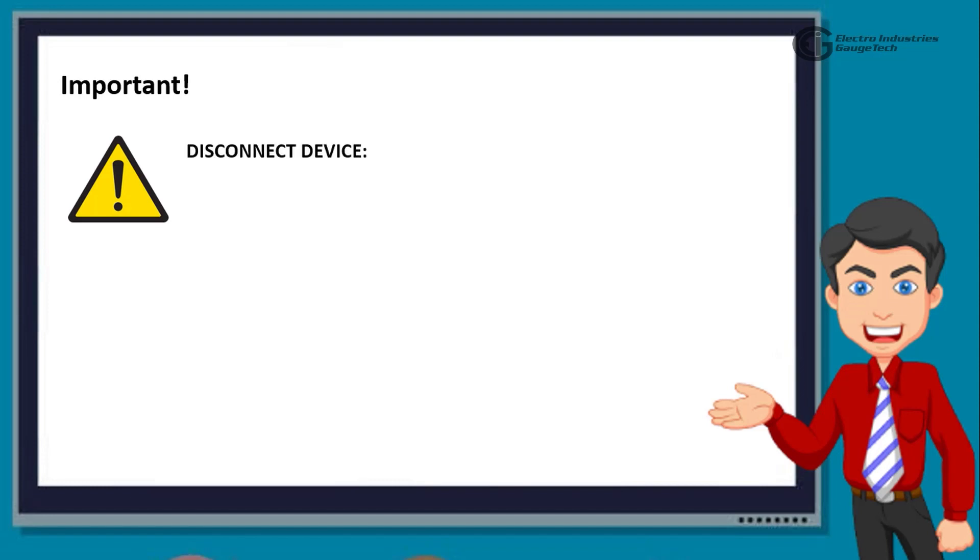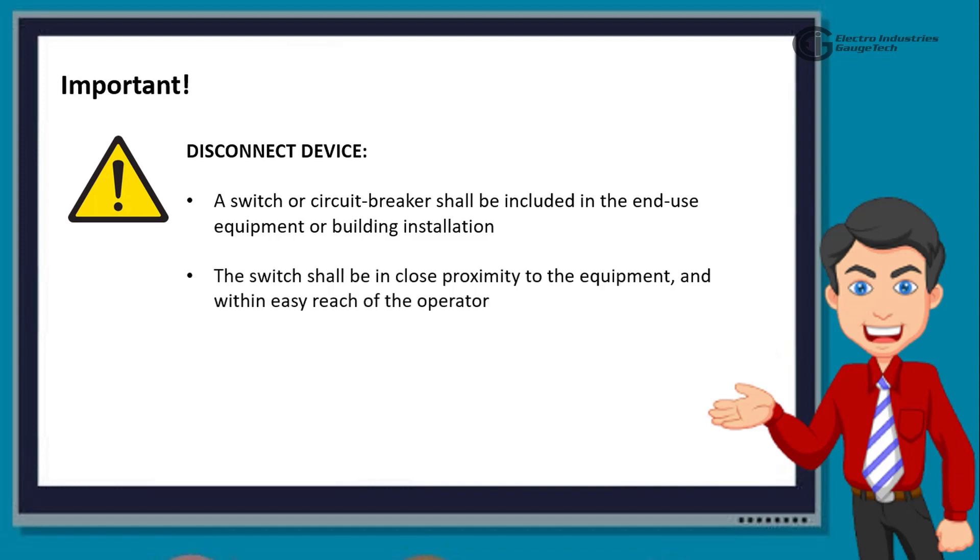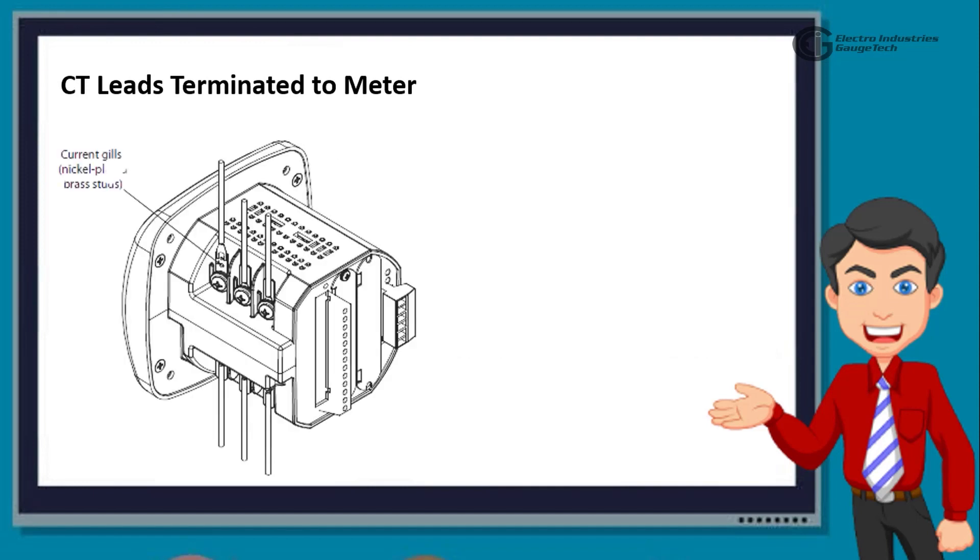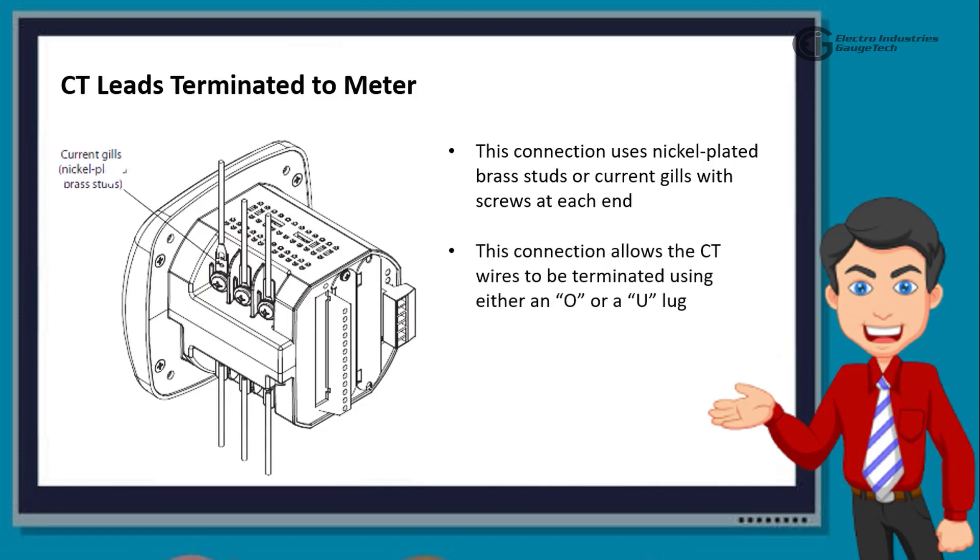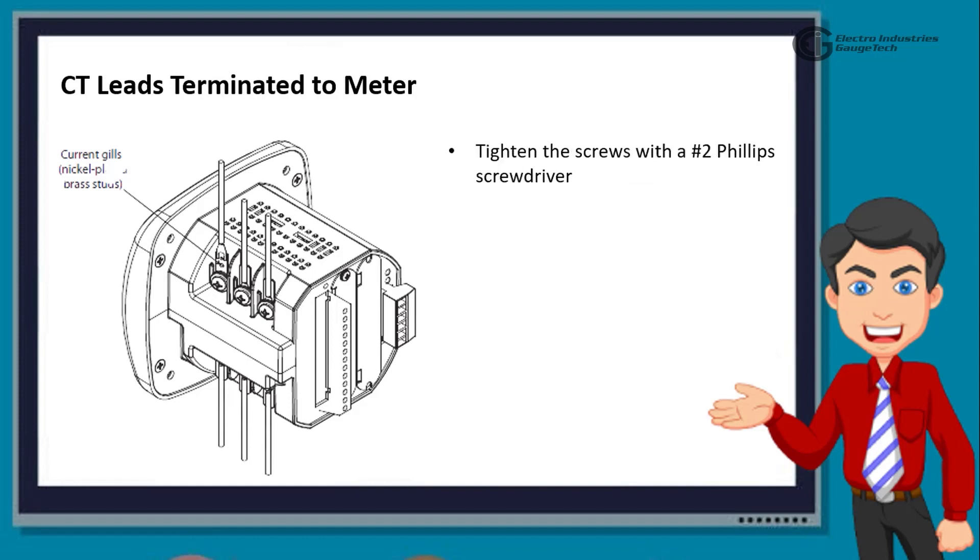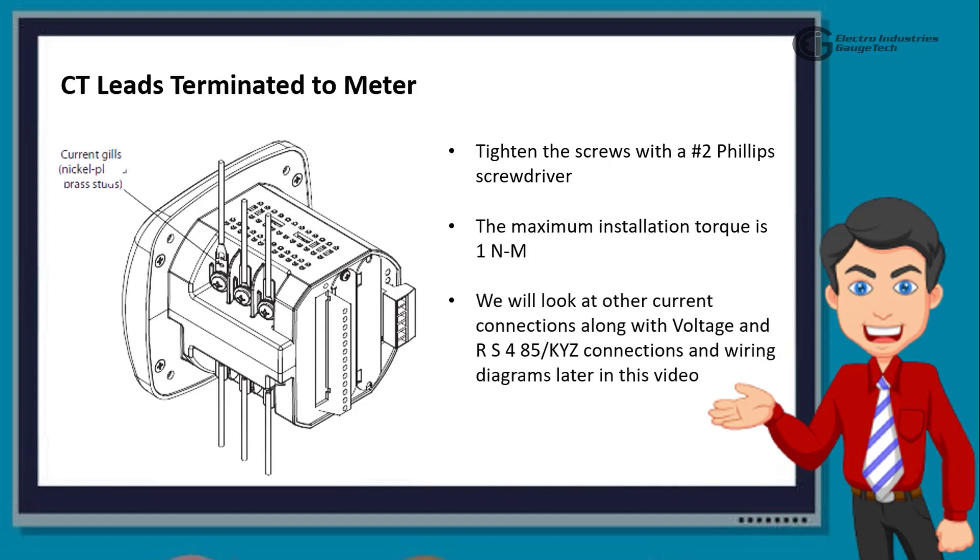Now, let's talk about the disconnect device which is an important part to be considered here. A switch or circuit breaker shall be included in the end-use equipment or building installation. This switch shall be in close proximity to the equipment and within easy reach of the operator. This switch shall be marked as the disconnecting device for the equipment. Next, we move to the CT leads terminated to meter. If you look at the image here, it shows the most typical connection where CT leads are terminated to the meter at the current gills. This connection uses nickel-plated brass studs or current gills with screws at each end. This connection allows the CT wires to be terminated using either ring or a U-lug. Tighten the screws with a number 2 Phillips screwdriver. The maximum installation torque is 1 Newton meter.